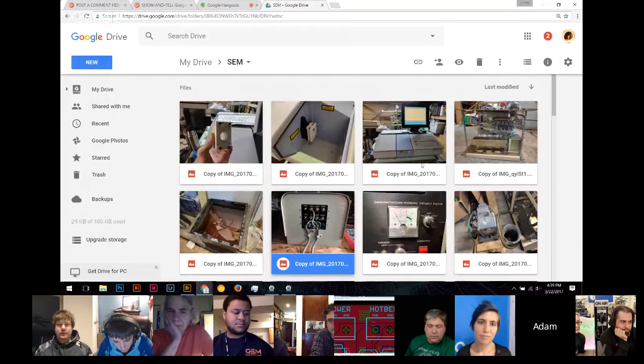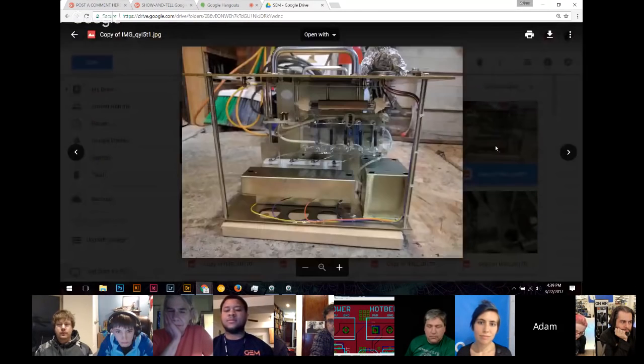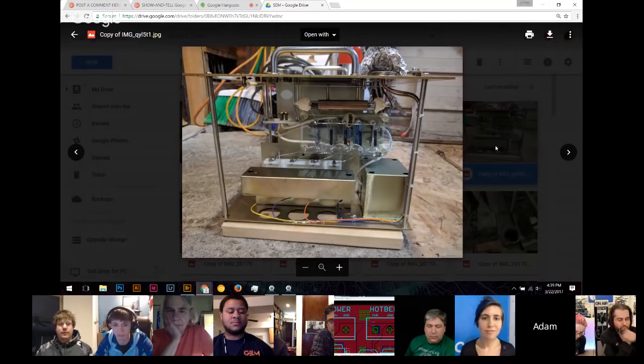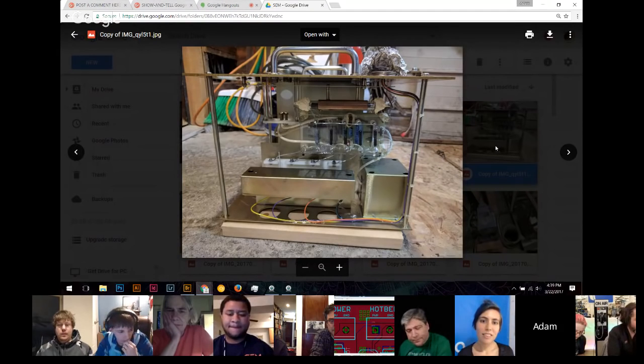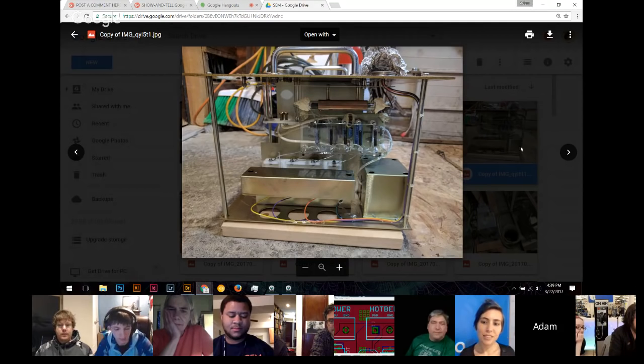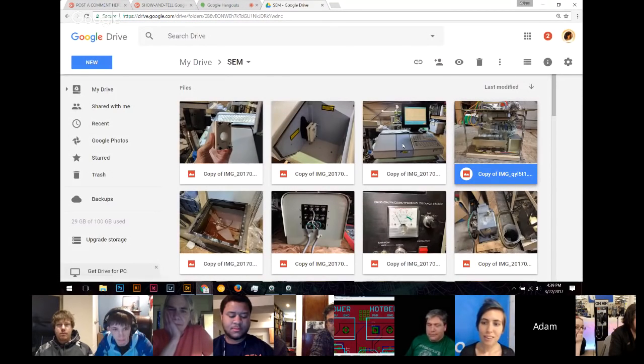And the last big thing was the high voltage system. This microscope requires 25,000 volts to accelerate the electrons to the point where you can actually make an image with it. So it uses what's called a Cockcroft-Walton step-up ladder to get it up to that kind of level, but the whole thing's submerged in this oil.